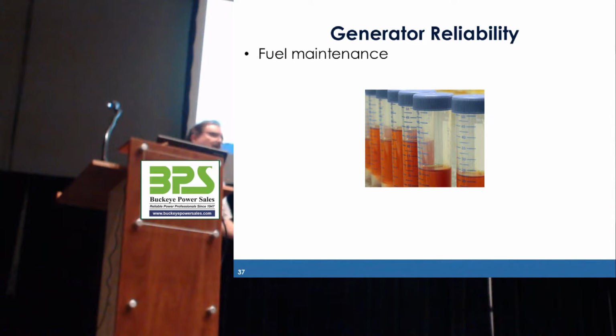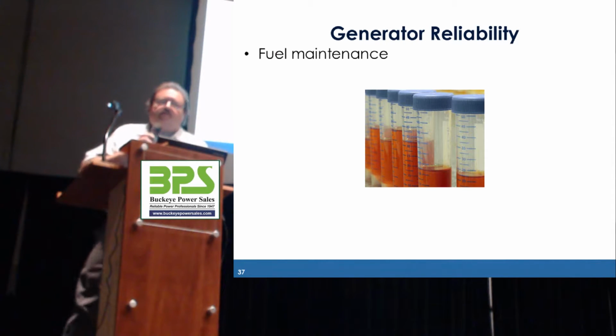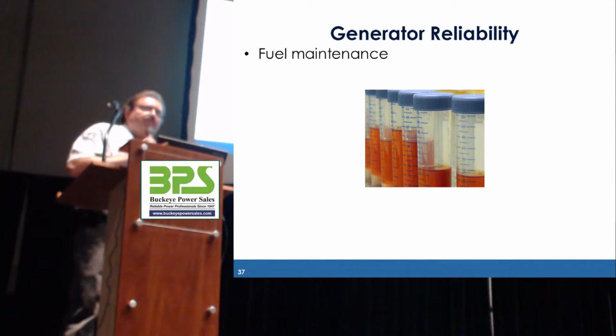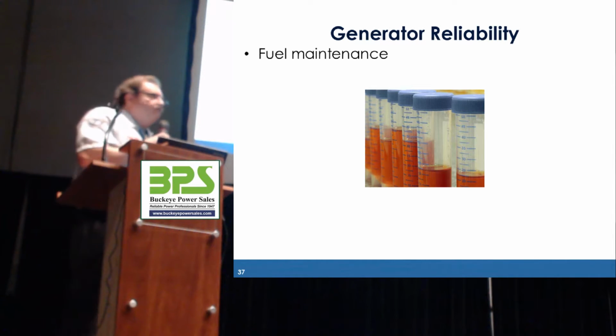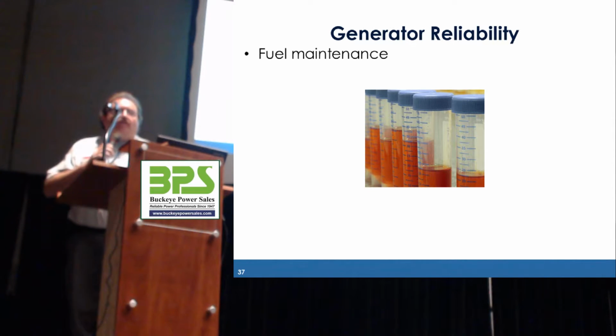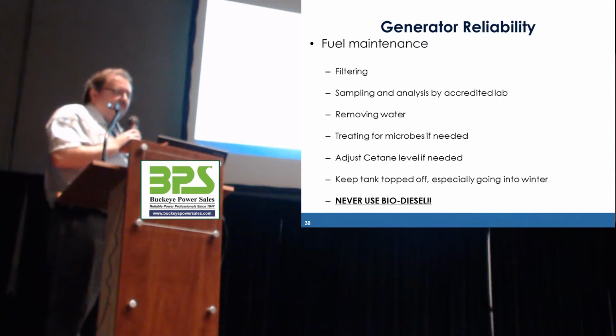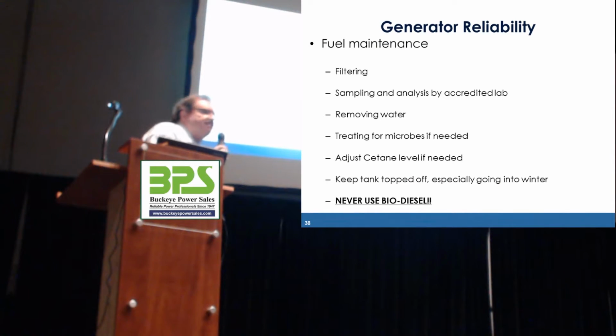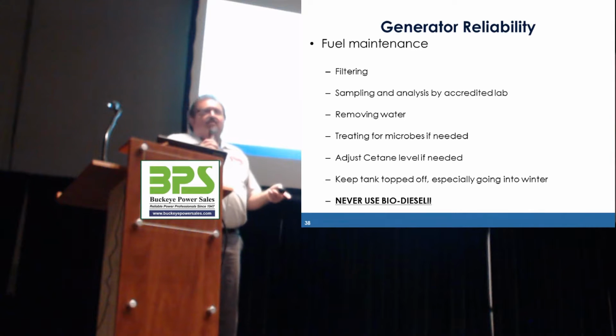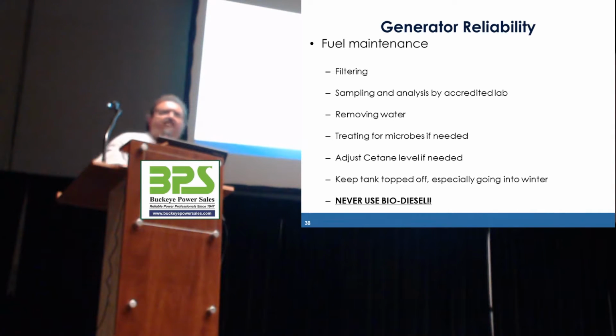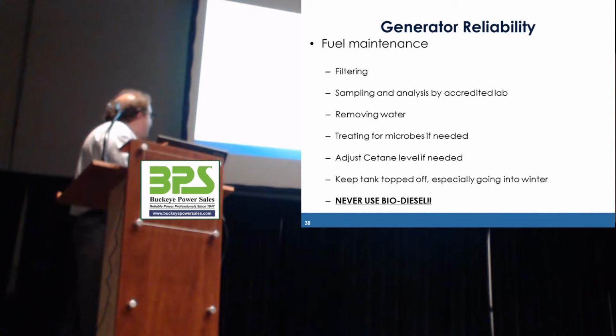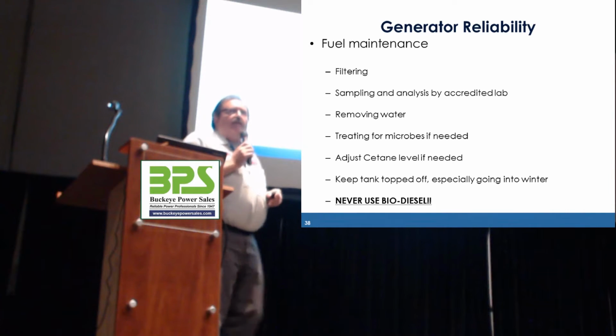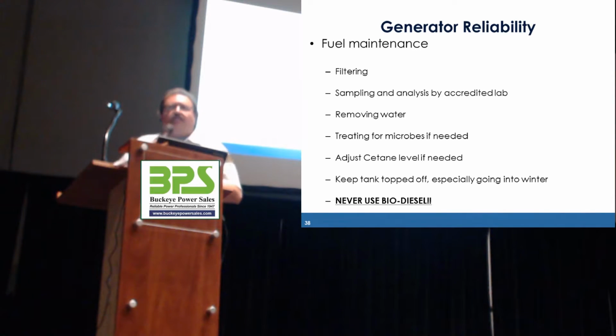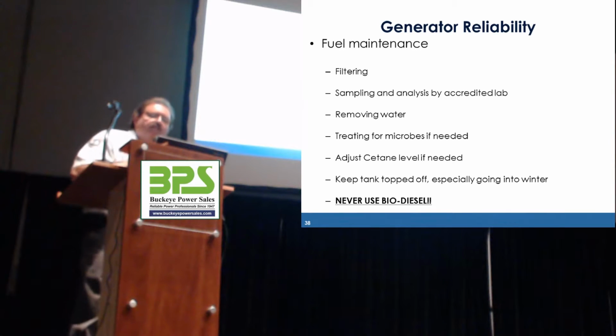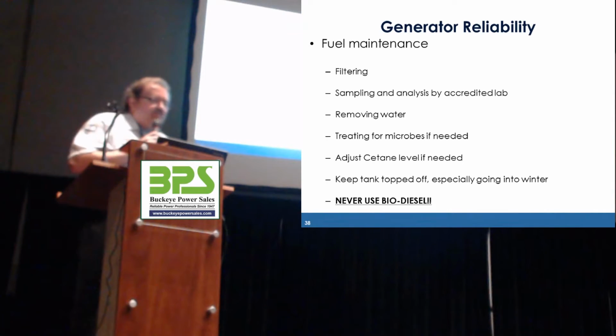One of the things that gets a lot of neglect on generators is fuel maintenance. Now, a lot of you here are doing fuel sample testing, which is good, and hopefully then that means along with that, you're doing the rest of the maintenance that needs to be done to the fuel. So you draw a sample, you have it tested, and it says it's dirty. Okay, that's a relatively simple process. You can filter the dirt out. You have it sampled by an accredited lab, and it comes back that there's water in the fuel. Okay, that's relatively simple. You can draw the water off. Usually you're doing that at the same time that you're filtering it. The same machine will do both.